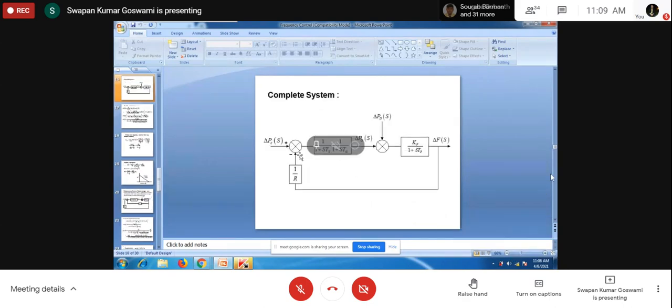At this point, that means the complete block diagram transfer function of the load frequency control system, including the generator, load, governor, and turbine. And this is the complete transfer function. Input is the speed changer position of the governor, through which we can give power increase or power decrease command. And the other input is obviously the change in load.